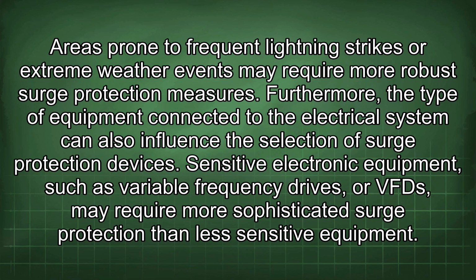Areas prone to frequent lightning strikes or extreme weather events may require more robust surge protection measures. Furthermore, the type of equipment connected to the electrical system can also influence the selection of surge protection devices. Sensitive electronic equipment, such as variable frequency drives, or VFDs, may require more sophisticated surge protection than less sensitive equipment.